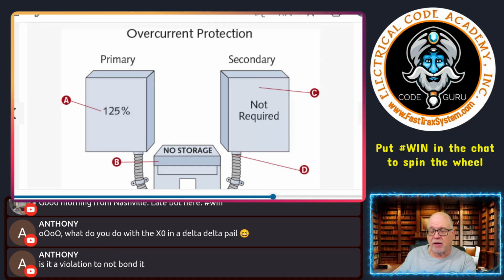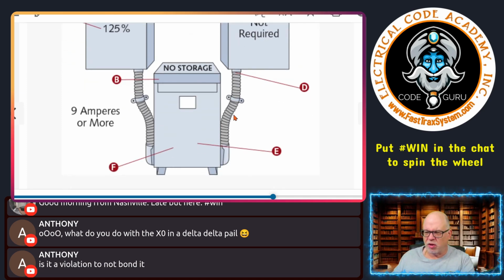So for the transformer's purposes, you may think the code says I have protection on the primary, but I'm not required to protect that transformer on the secondary, because of what size it is or what the table tells you. But if you happen to be supplying a panelboard, then you have to worry about the protection of that panelboard. So it will require some type of overcurrent device in that panelboard, because you have to protect the panelboard. Those are the kinds of things we're going to look at.